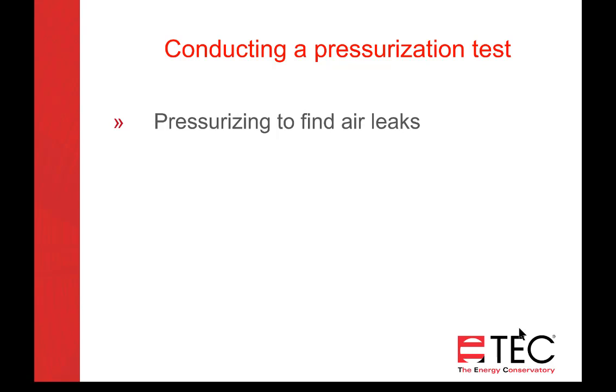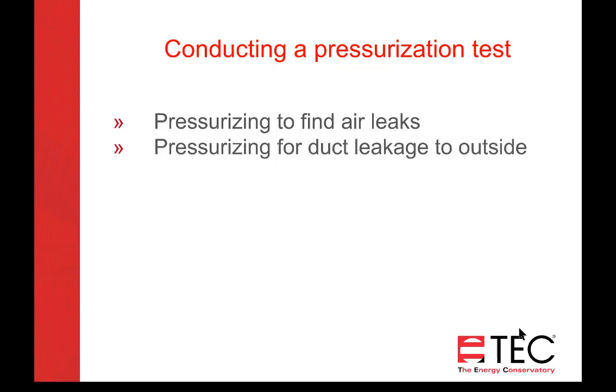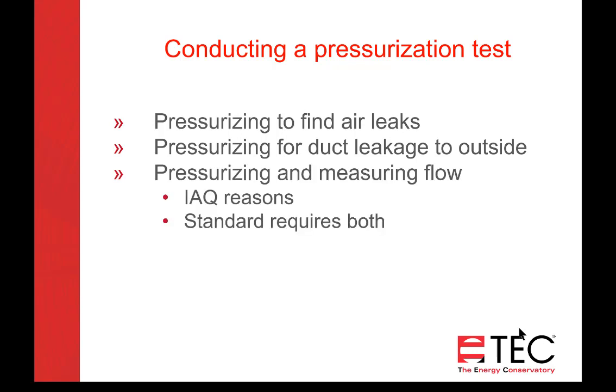So pressurizing, some people pressurize to find air leaks. If you're doing a duct leakage outside pressurization test, then you'll be pressurizing the house and the duct work at the same time. Our older fans, if you've got a fan that's older than 10 years old, it will have a forward reverse switch on it. And you can use that reverse position if you're not measuring airflow. And in these two cases, you wouldn't be using it to measure airflow. So you could use that switch on the fan to pressurize the house. But if you're pressurizing and measuring flow, then you can't use that forward reverse switch.